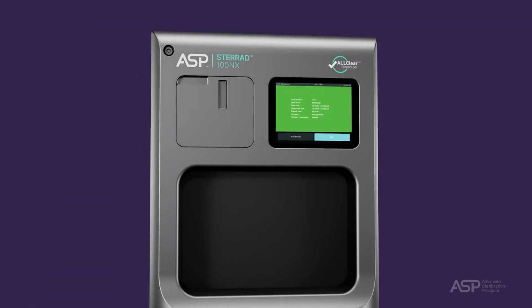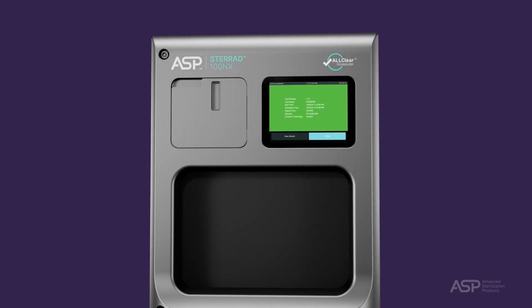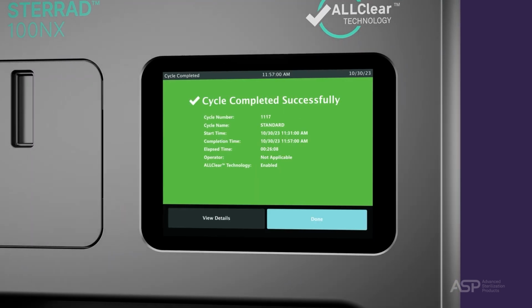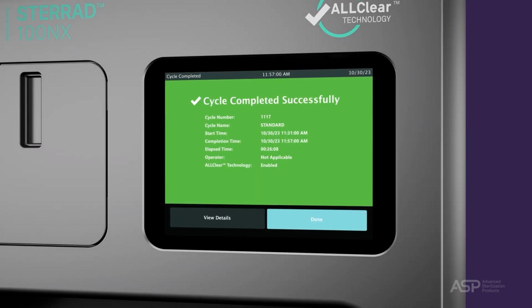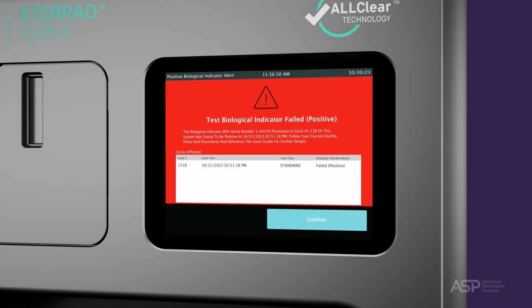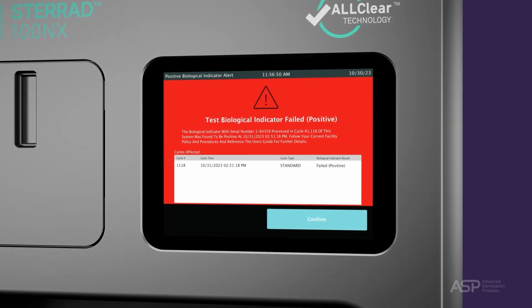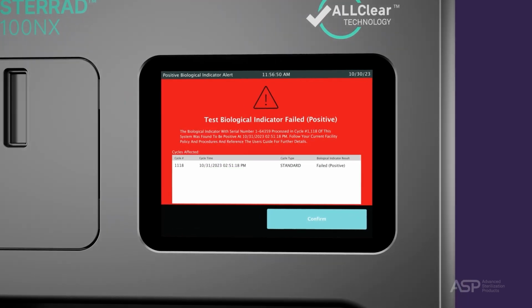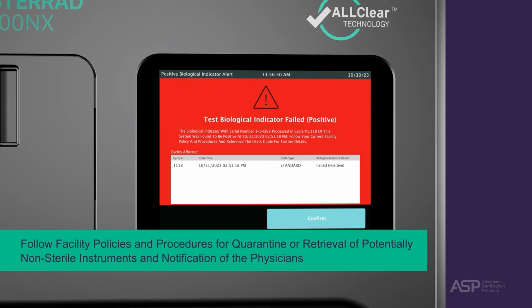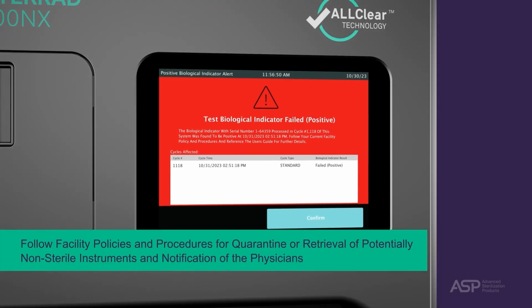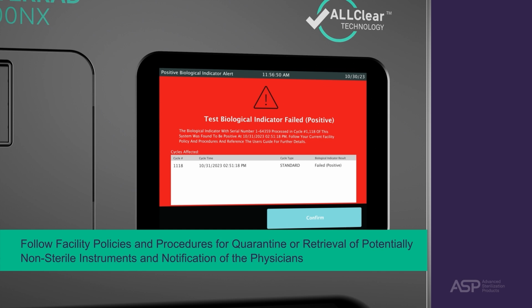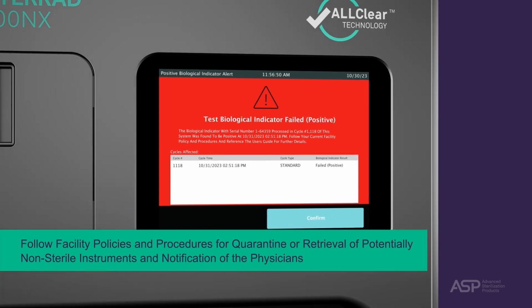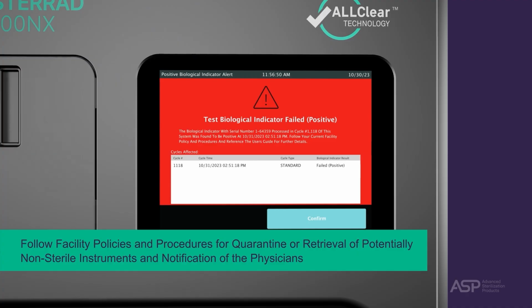If your STERRAD system is integrated with a STERRAD Velocity Reader, the user will not be notified of negative test biological indicators. The sterilizer will be alerted when the STERRAD Velocity Reader detects a positive test biological indicator. Follow the current hospital or healthcare facility's policies and procedures regarding quarantine or retrieval and reprocessing of potentially non-sterile instruments and notification of the physicians.